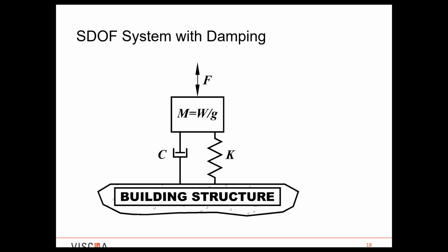I painted the illustration of having equipment on a slab, outside a hospital building. And that slab ideally is not moving. It is bearing on the soil and it's just the equipment that is moving. So you just have a single degree of freedom system with damping here in this illustration. And so on the right is your spring constant, your K, and here is your damper through a dash pot or a Coulomb damper that's providing some damping to your mass here that is moving. So that would be a single degree of freedom system.